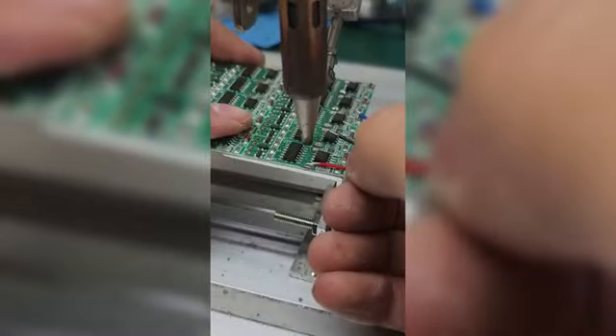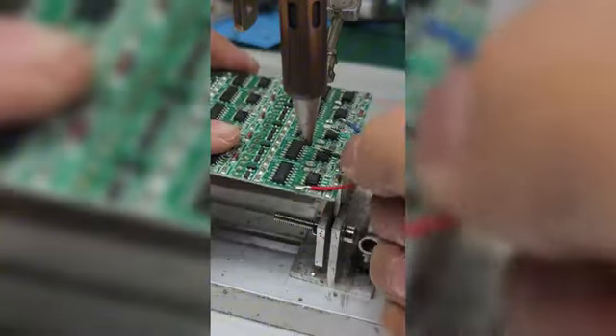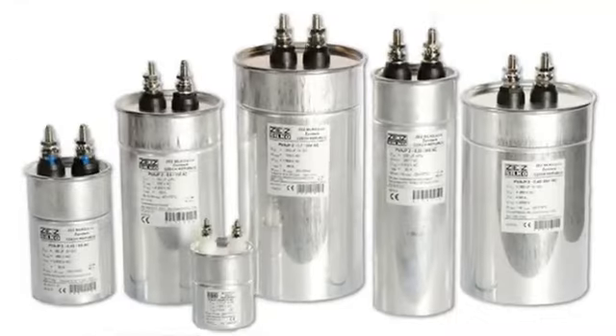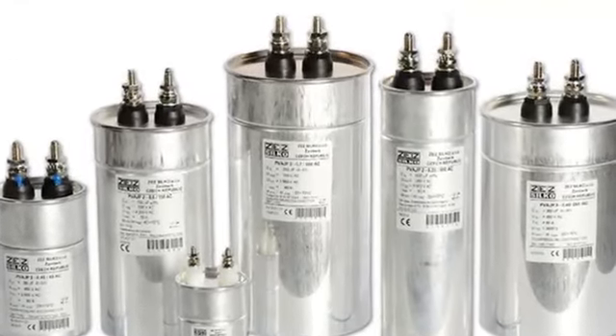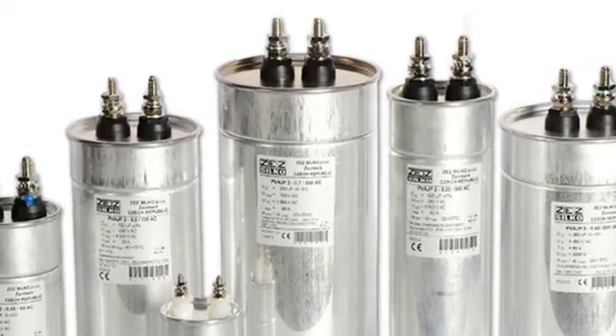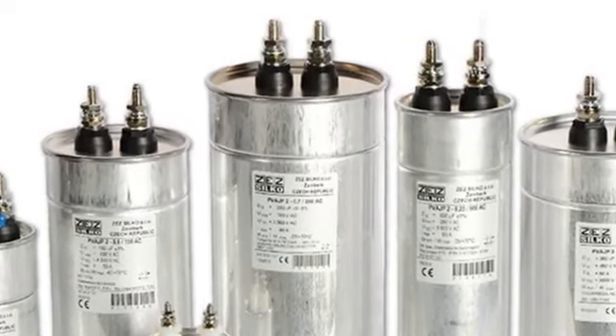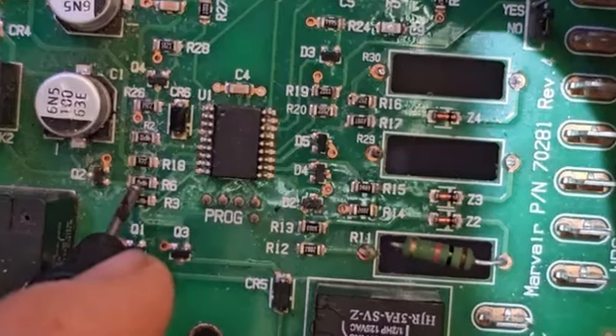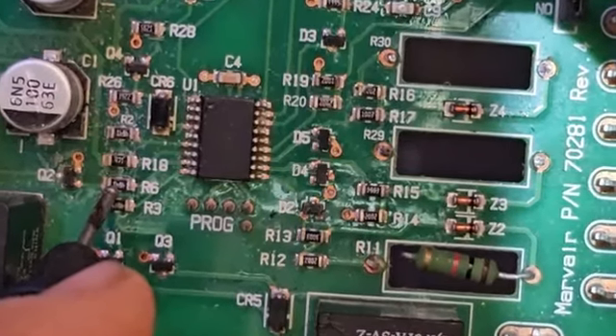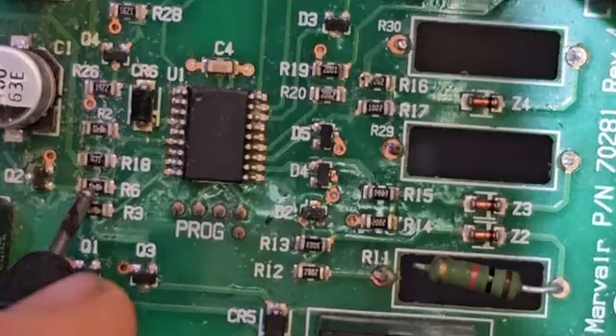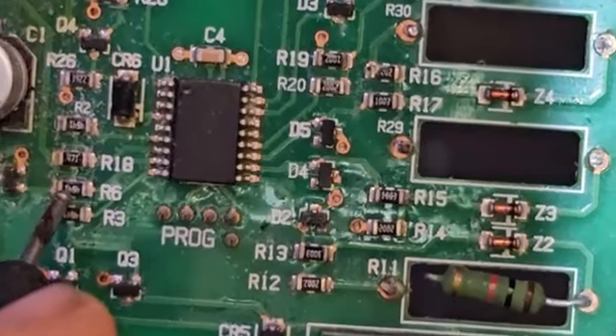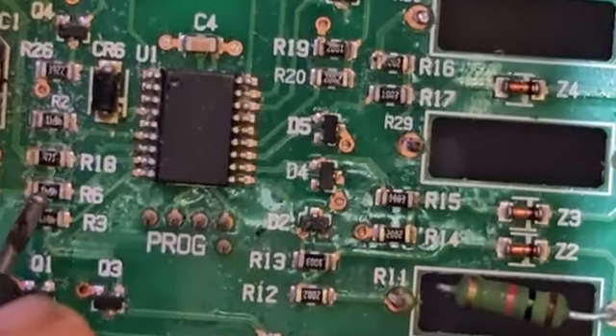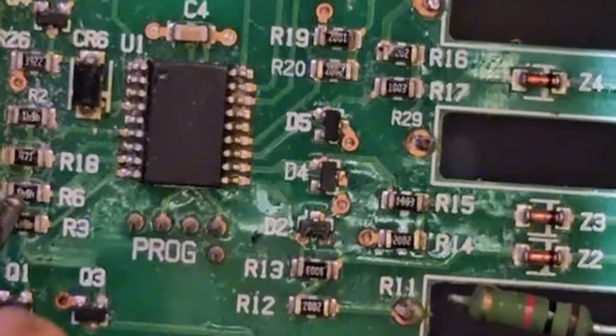The failure point is the control board. Circuit boards and attic air handlers experience temperature swings from 30 degrees in winter to 150 degrees in summer. Capacitors on those boards are rated for 105-degree operating temperatures. They fail in 5 to 8 years. When a control board fails, the system does not limp along. It stops. No cooling, no heating. You do not notice gradual decline. You wake up and the house is 85 degrees.